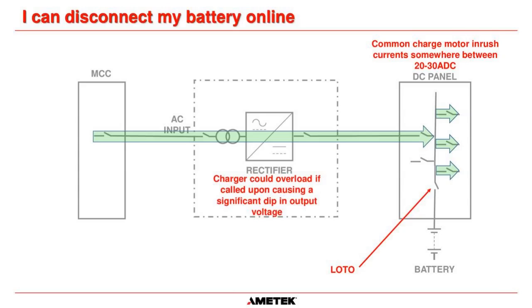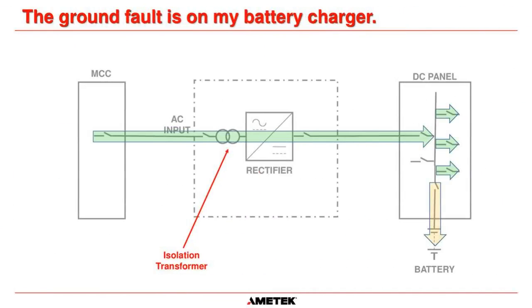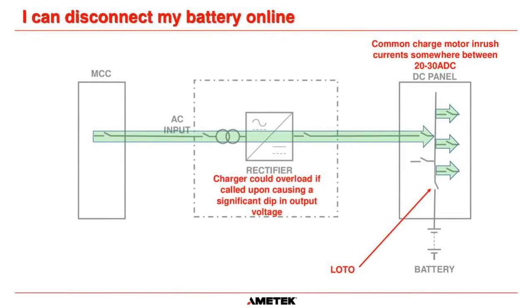So the best thing to do, if you ever have a battery failure, is hopefully your engineer has designed in an additional breaker. Then you can come in, get a temporary battery and connect it onto that breaker there. That will allow you to open this breaker and replace this battery here, and you now have a temporary battery that is going to maintain power if you have a power loss or if your tripping and closing coil springs are called into action. But do make sure that this temporary battery is exactly the same ampere hour capacity as the battery that you are replacing. Okay.